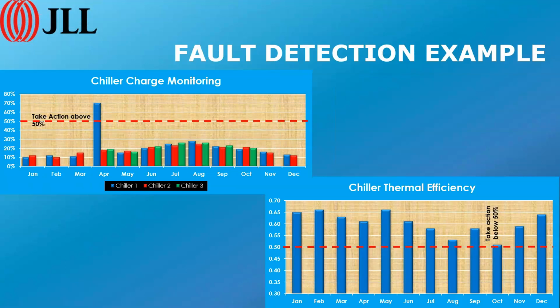In this case, and other similar cases, we'll have the system send out an alarm, and then when the service tech shows up, we just tell them that we were monitoring delta P over P, and it's way high, and that's why you're out here. So he'll start looking around. On this chiller, it turned out that there was a leak at a service valve. Not a big deal, but we caught it long before there was a problem. That was a 500-ton compressor, and there were 3 of them in there, so it was a 1,500-ton machine. It had 800 pounds of refrigerant in it, total charge, and it was down by about 30 pounds. So we were able to pick that up pretty quickly.